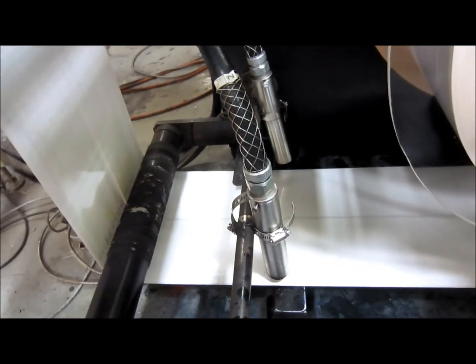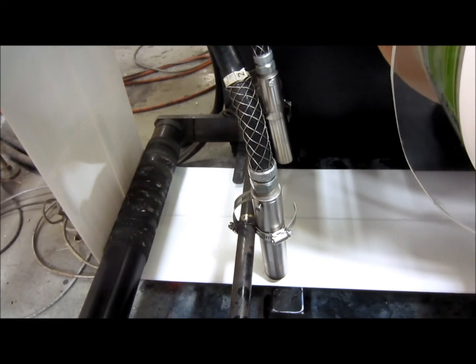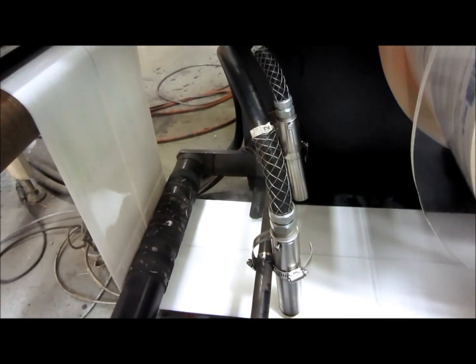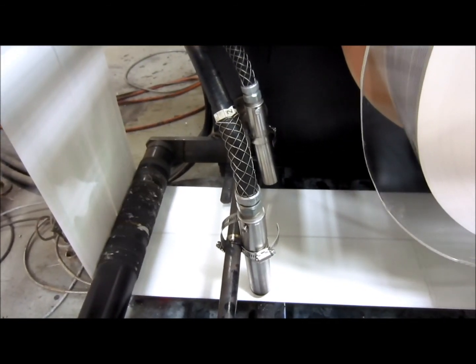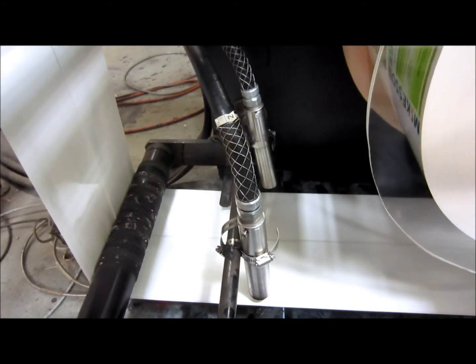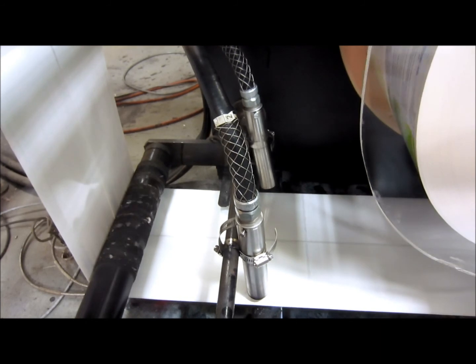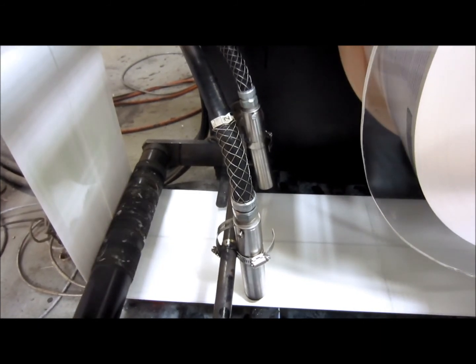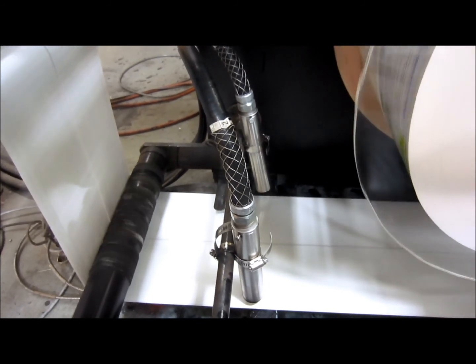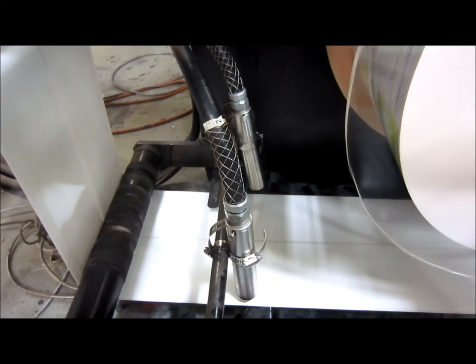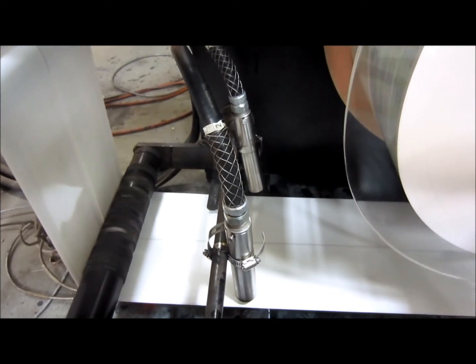This is a TRD series rotary encoder, and it is used to pass information about exactly how fast the machine is moving onto a continuous inkjet printer. The inkjet printer is used to provide numbering on the back of the label, and the purpose of that is so that it can print at the same intervals, the same character size, regardless of the speed of the machine. Go ahead and speed it up. You can't even see it at that speed, but it's printing the same now as it was at slower speed.